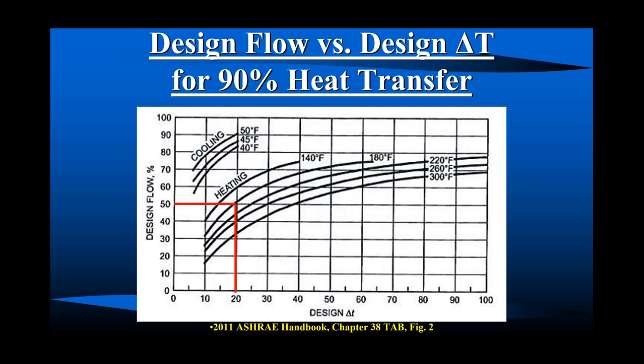Very tolerant system. And that is why there's a whole bunch of people saying out there, mostly contractors, who say this is a self-balancing system because it's so tolerant. You can be off by half and still get 90% out of it. And there's probably some fudge in there. So your design day, if you get there at all, right, 2% of the time. So rarely does it come into play. And that is why many contractors say it's self-balancing, as if your heating system had a self. So nothing is self-balancing. It's just very tolerant. And the 180 to 160 system is extremely tolerant.